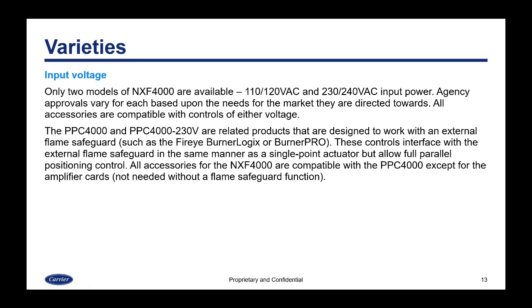The PPC4000 and PPC4000 230-volt are related products that are designed to work with an external flame safeguard, such as the FireEye Burner Logix or the FireEye Burner Pro. These controls interface with the external flame safeguard in the same manner as a single-point actuator would, but allow full parallel positioning control. All accessories for the NXF4000 are also compatible with the PPC4000, and that's what we're going to go over in this presentation, except for the amplifier cards because those are not needed with the PPC4000. And there's a separate presentation available on the YouTube channel that goes into detail about how the PPC4000 interfaces with a flame safeguard.